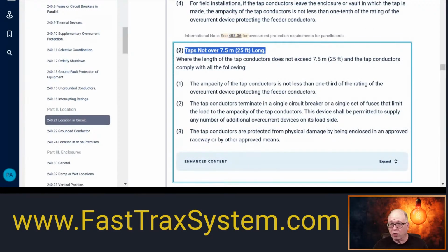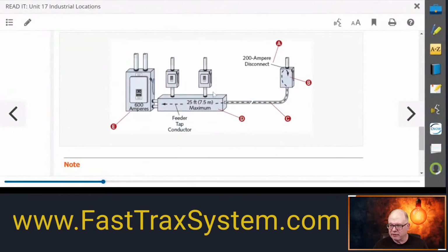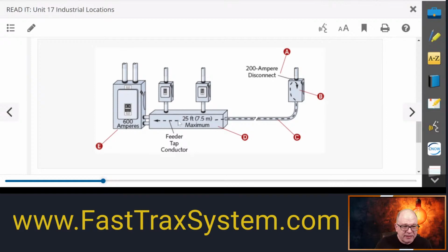Okay. So what are we talking about? Let's bring you back. So here's what we're talking about right here. Okay. So we're making a tap here. Here's the feeder. Okay. And we're making a tap here. And then this, again, here it's going not more than 25 feet. Now, remember something I told you last week? A tap right here, a feeder tap, does not have to tap a conductor, folks. Okay? I don't know if I can blow this picture up a little bit. There we go. It does not have to tap a conductor in here. Okay? This could be the load side lugs of this device right here. And you can still apply the tap rules.